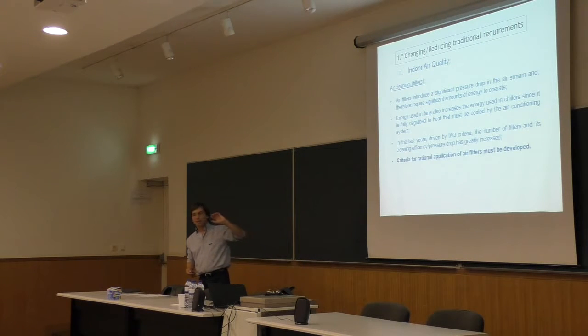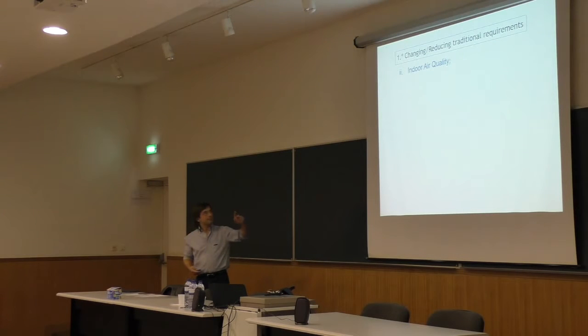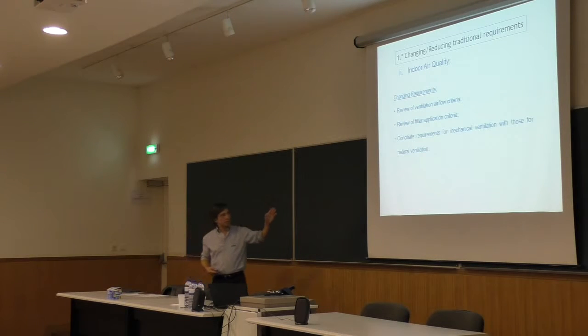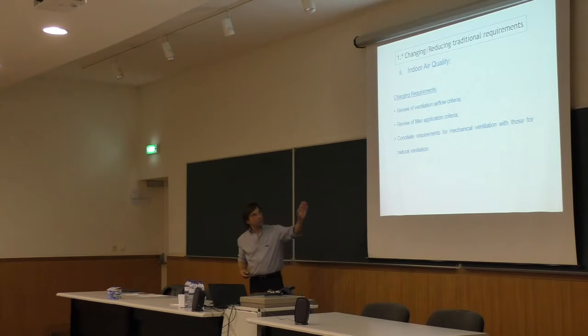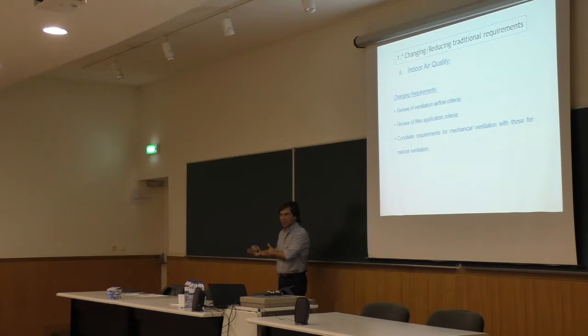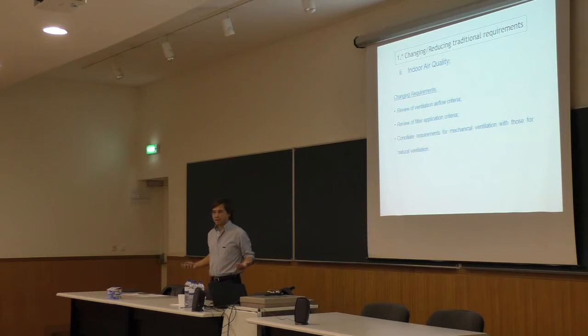So we also need good criteria for indoor air quality. We have to review ventilation airflow criteria, review filter application criteria, and conciliate requirements for mechanical ventilation with those for natural ventilation. It makes no sense that when using a mechanical ventilation system we need huge filters with high energy consumption, but we can also open windows. When you open a window, outside air comes directly inside the building. Why clean it with high efficiency filters when using a mechanical system? It makes no sense.